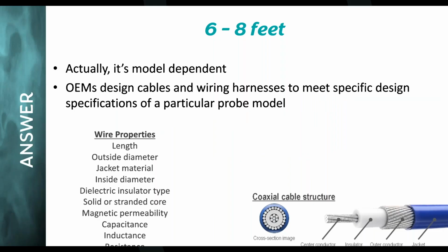And so we actually fabricate, we're up to 145 different cables based on the OEM electrical performance, its resistance, capacitance, reactive capacitance, we call it. It's down to the length, the diameter, the color of the cable sheath, the materials, all those things. So when a sonographer gets that probe back, it will look and operate and perform as a new one from the OEM. And that sonographer may take note of a shorter cable.